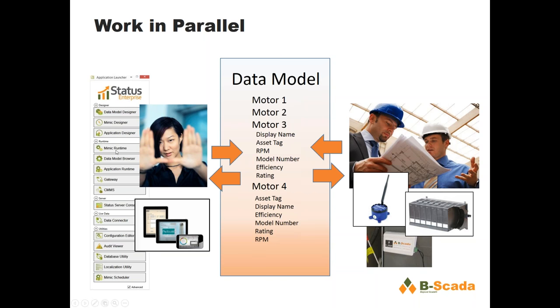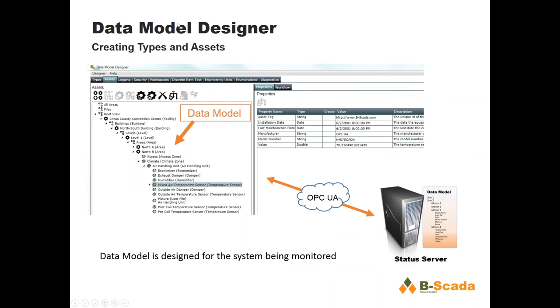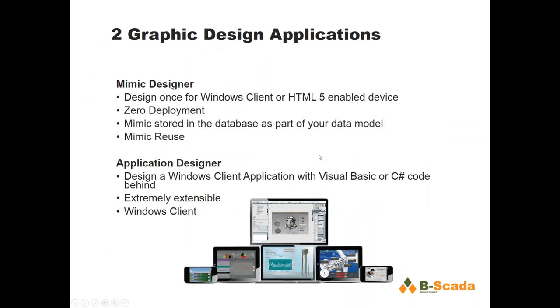All of the Status Enterprise client applications talk to the model directly — none of them know anything about sensors, Modbus addresses, PLC addressing, or anything like that. That data model shows up in all client applications. Here we have the data model designer, where we actually build the model. Building a model is simple: you define a type, like a pump, add properties to that type, then create instances of those assets — the real-world things you're monitoring. That data model is stored in your Status server, whether in the cloud or behind your firewall.